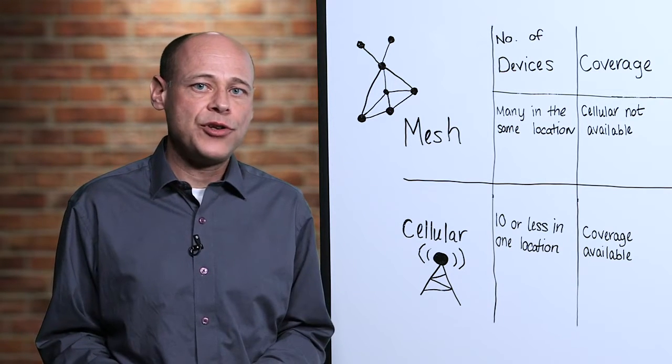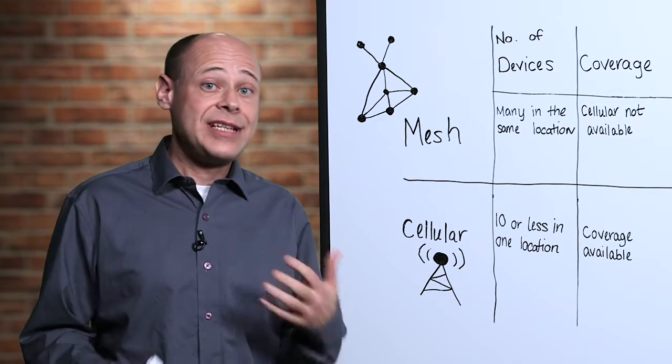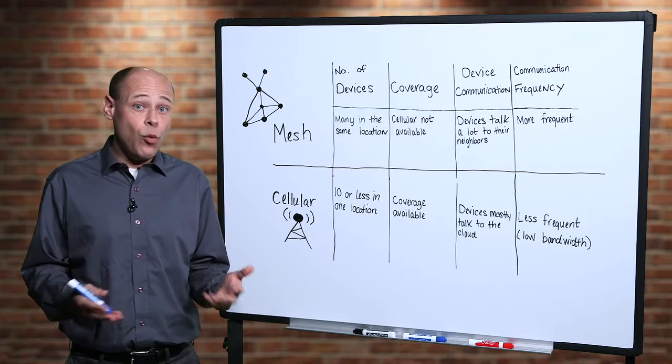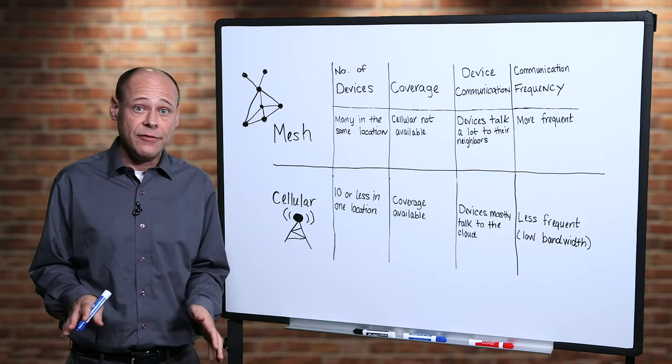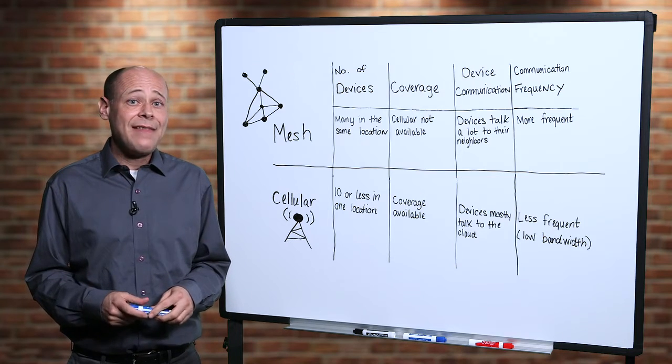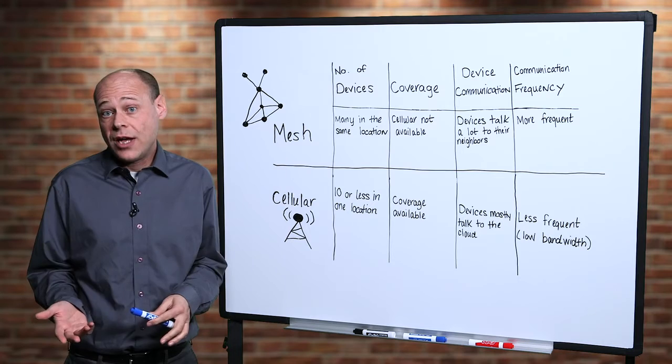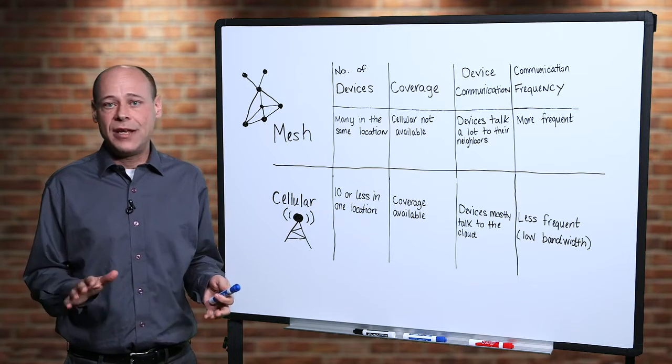Cellular is a popular choice for applications like tank monitoring. Let's say diesel fuel tanks for emergency generators. You'll want to know the current condition and fuel level of each tank. There are typically few nodes per location and they only need to communicate once in a while to state the current fuel level or to send an alarm if there's trouble.